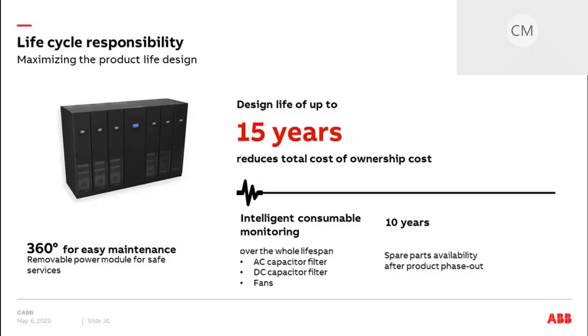Okay, great. Another question I have for you, Diana. For the UPS, are the power modules online swappable? Yes, if there is a need to maintain a UPS module, then it can be removed without transferring the other modules into the bypass mode. Then the load is always protected in double conversion mode by the remaining modules. This is what we call online swappability.